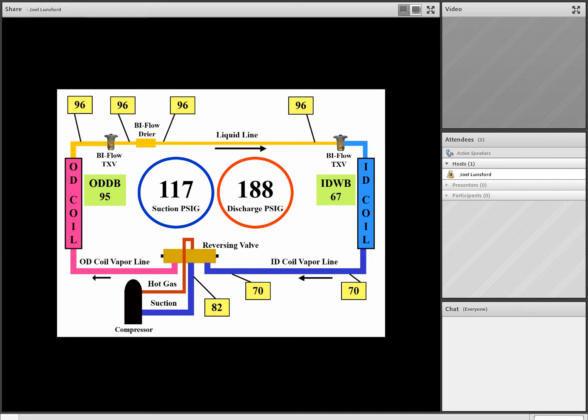Now, we talked about that earlier in our previous modules as far as the reversing valve and what the temperature difference across it should be, and we should never exceed about 4 to 7 degrees across a reversing valve. But in our example here, we've got a 12-degree temperature difference between the two cool lines of the reversing valve, coupled with high suction pressure. So anytime you have high suction pressure and a big temperature difference across the two cool lines of the reversing valve, we know that reversing valve is leaking and it needs to be replaced.